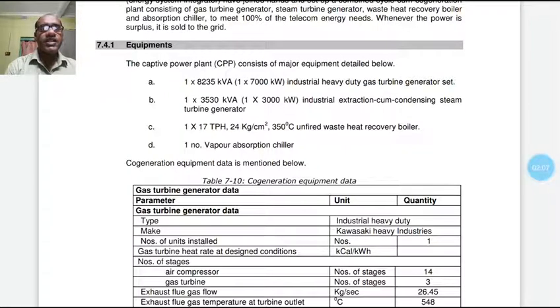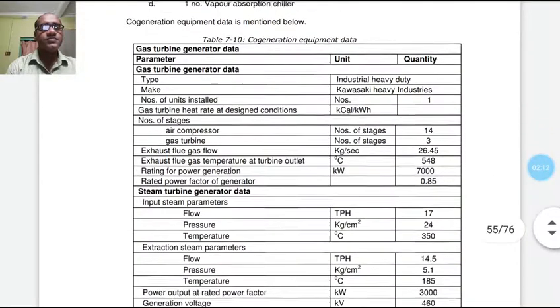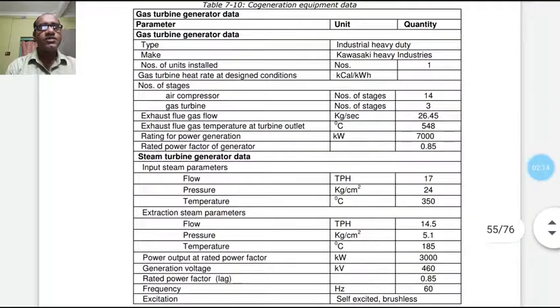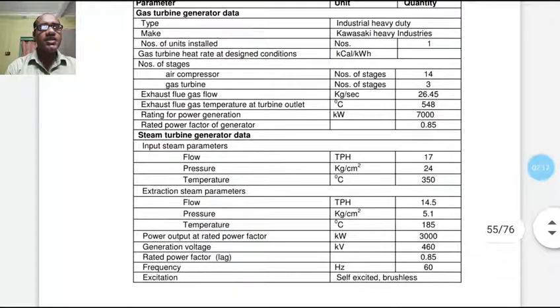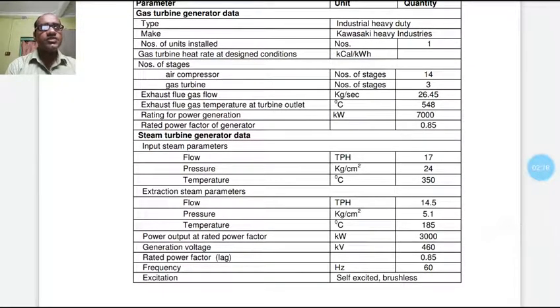Cogeneration equipment data are maintained and given. For the gas turbine, the maker is Kawasaki Heavy Industries. Air compressor number of stages 14, gas turbine number of stages 3. Exhaust flue gas flow 26.45 kg per second. Exhaust flue gas temperature at turbine outlet 548. Rating of power generation 7000 kilowatt. Rated power factor for generation 0.85.